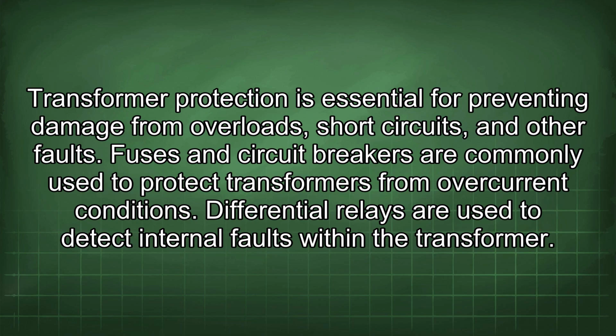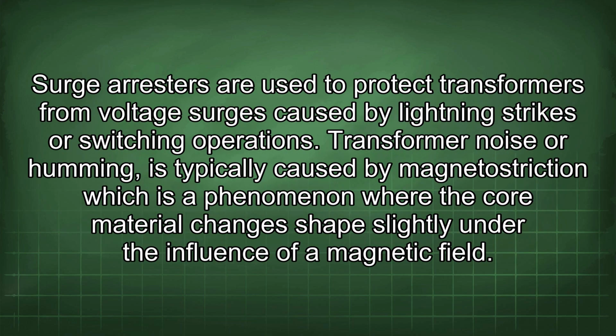Transformer protection is essential for preventing damage from overloads, short circuits, and other faults. Fuses and circuit breakers are commonly used to protect transformers from overcurrent conditions. Differential relays are used to detect internal faults within the transformer. Surge arresters are used to protect transformers from voltage surges caused by lightning strikes or switching operations.